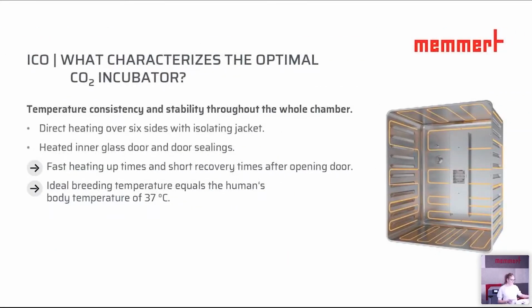All right, moving on to what actually characterizes the optimal CO2 incubator. Well, to pick up the first requirement, the temperature, we of course want temperature consistency and stability throughout the whole chamber. Memmert provides this with a direct heating system over 6 sides, the left, the right, front and back, and also ceiling and bottom, of course, with an isolating air jacket. To provide a heated front, we also have the inner glass door, which is heated, and heated door sealings to prevent uncontrolled and unwanted condensation.